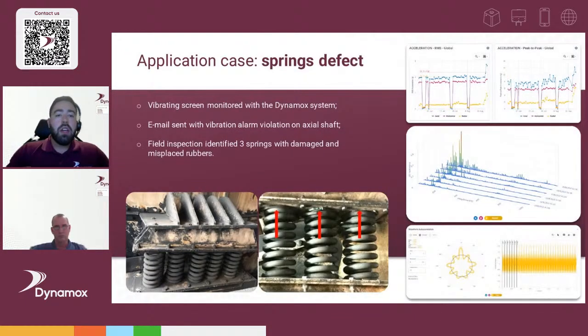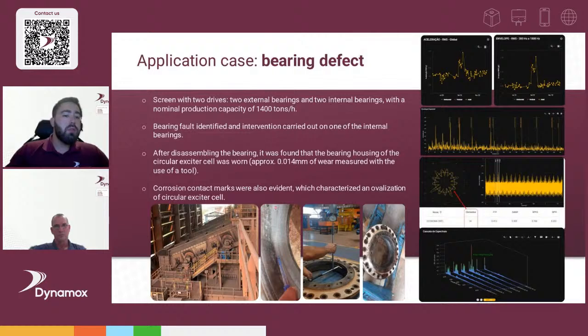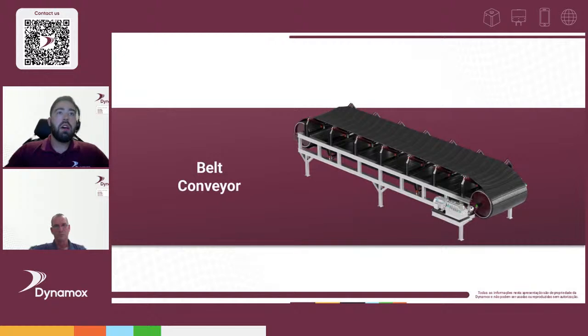Screen dashboards support two analysis modes: performance for production and process teams, and structural health for maintenance. We can extract linear motion and circular or elliptical orbit data. A real success case showed a broken spring defect: the overall trend behavior changed, an alarm was sent by email, the customer investigated and found the problem. The same approach applies to bearing defects — behavior change triggers notification, and the dashboard identifies the most likely failure mode.